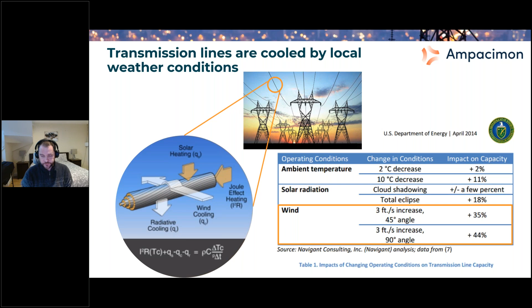So now we get into the different types of ratings that are used around the world. Starting at the top, your typical rating is static line rating. This is when you buy a conductor, you'll get a data sheet that comes with it, and it says, this is what it's designed for, do not exceed this value. And that's conservative. It has to assume the hottest time of the year, no wind. It's very, very conservative. Many utilities for a number of years, decades even, have used seasonal adjusted ratings, where they take into account the fact that winter is a lot colder than summer, and they essentially use different weather parameters to determine the rating in the middle of winter and the middle of summer, and they swap over between the two. So you land up with a higher rating in winter, lower rating in summer typically.